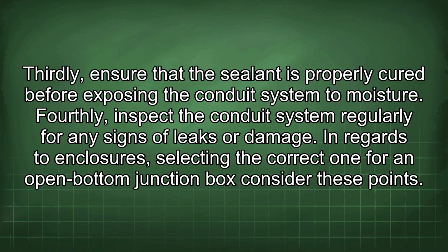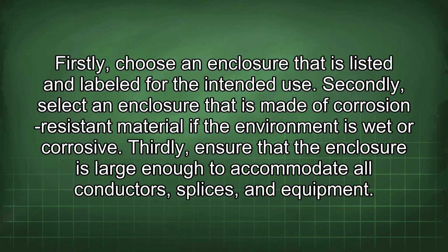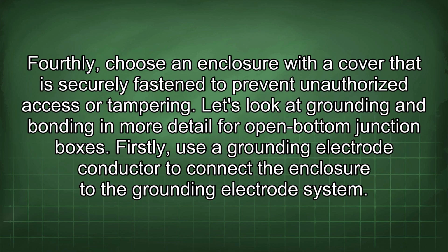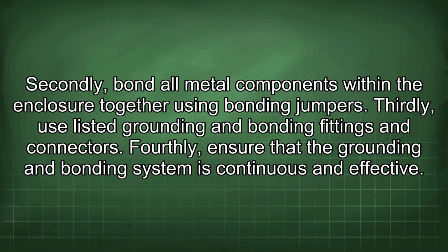In regards to enclosures, selecting the correct one for an open-bottom junction box, consider these points. Firstly, choose an enclosure that is listed and labeled for the intended use. Secondly, select an enclosure made of corrosion-resistant material if the environment is wet or corrosive. Thirdly, ensure that the enclosure is large enough to accommodate all conductors, splices, and equipment. Fourthly, choose an enclosure with a cover that is securely fastened to prevent unauthorized access or tampering. Let's look at grounding and bonding in more detail for open-bottom junction boxes. Firstly, use a grounding electrode conductor to connect the enclosure to the grounding electrode system. Secondly, bond all metal components within the enclosure together using bonding jumpers. Thirdly, use listed grounding and bonding fittings and connectors. Fourthly, ensure that the grounding and bonding system is continuous and effective.